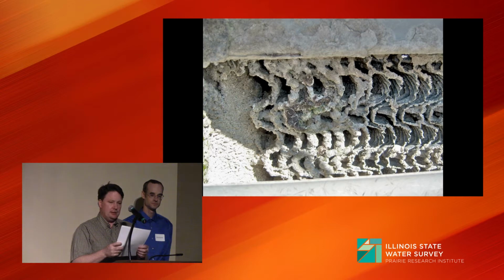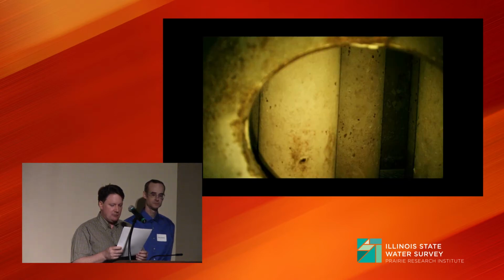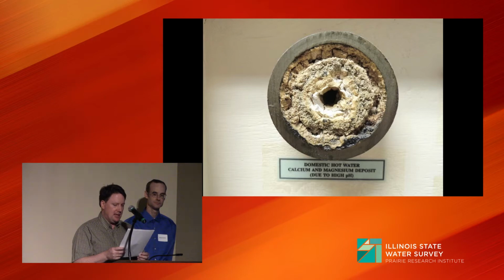These are vertical boiler tubes covered with scale due to improper water treatment. As little as 1/8 of an inch of scale can reduce boiler efficiency by 25%. Scale can also cause a boiler tube to rupture. Tap water can have scaling issues also. Calcium has the unusual property of becoming less soluble as the temperature rises. The severe scaling in this hot water pipe has rendered it unusable. This results in the costly reinstallation of new pipe.